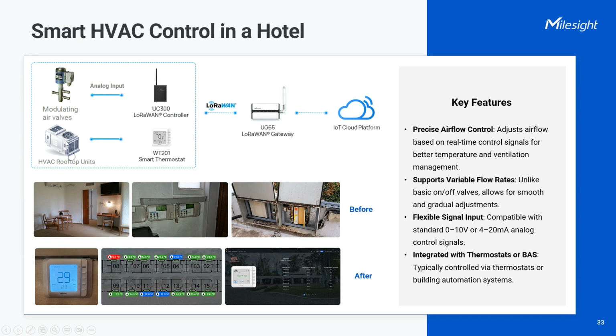Here's how it works. 16 smart thermostats were installed, one in each guest room, giving guests real-time room monitoring and personalized temperature control. An additional smart thermostat was installed at the reception desk, providing a general temperature reading for the common area. The WT201 transmits environmental data over the LoRaWAN network to a central management system, which calculates the required valve opening percentage, then sends that command to the corresponding UC300, enabling precise and dynamic airflow control.